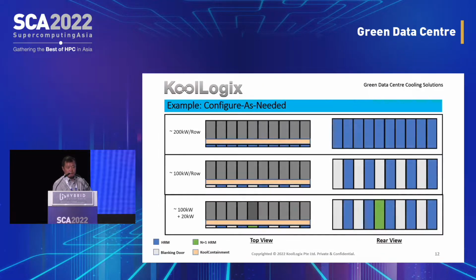Let me give you more examples. What if we have 200 kilowatts of heat dissipation from 10 racks? Then we have no choice but to provide 10 HRMs. But keep in mind, it doesn't have to be 20 kilowatts each rack. It's always the total heat dissipation through the racks sharing the KoolContainment that counts. So if the maximum heat dissipation everywhere is 200 kilowatts, we provide 10 HRMs. But if the entire row only dissipates up to 100 kilowatts, we only need 5 HRMs. This also highlights that we can have redundancy and/or additional heat dissipation capability.